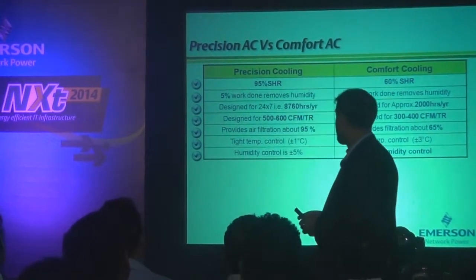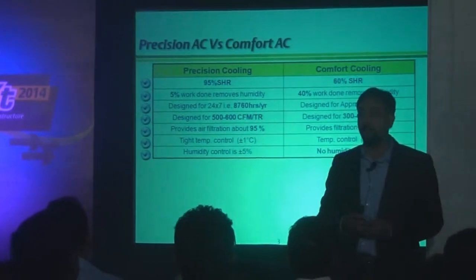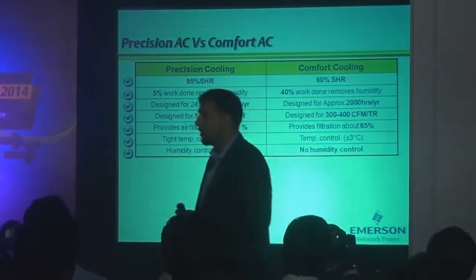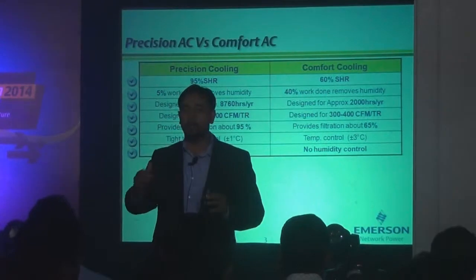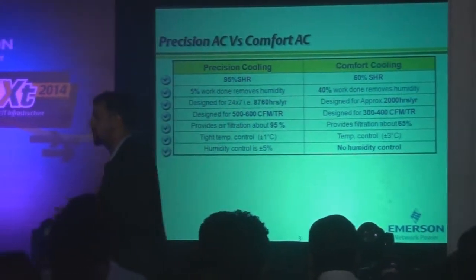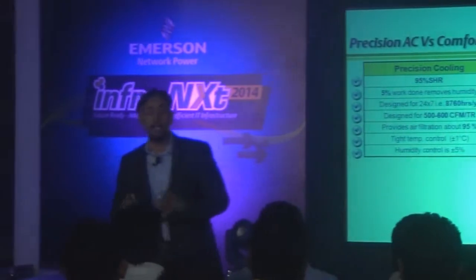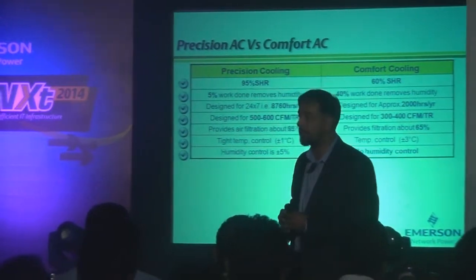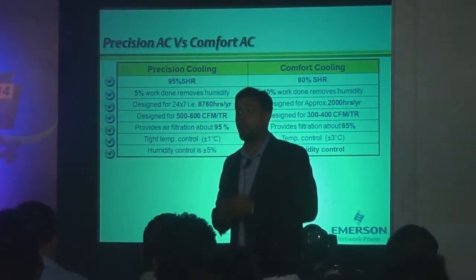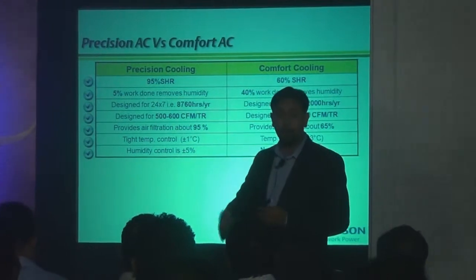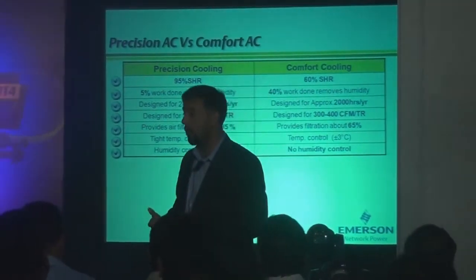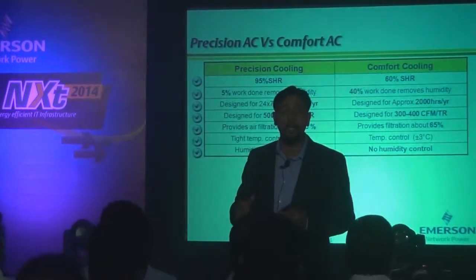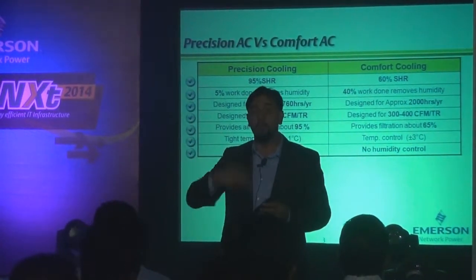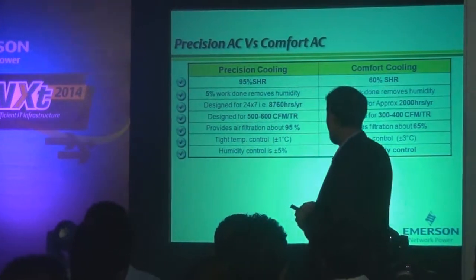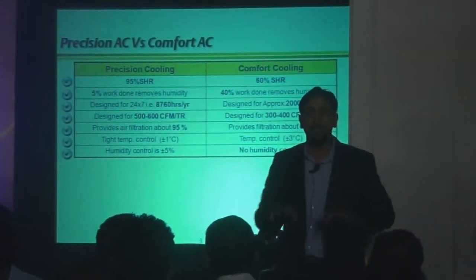Now we move to energy efficiency, which today is the subject everybody talks about. Precision ACs by design itself, compared to comfort ACs, are about 33 to 35% more efficient. So at the design level, for a server room or data center, it consumes about 33 to 35% less power compared to a comfort AC for the same application, and it delivers more airflow for the same tonnage. That means the CFM per TR is high, so it removes heat faster compared to comfort AC systems, and it maintains temperature and humidity very precisely.